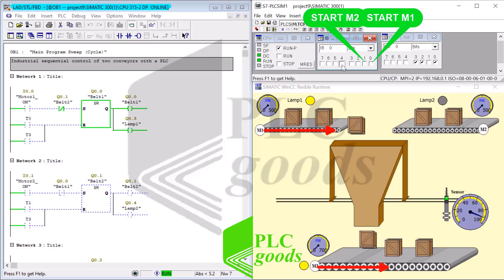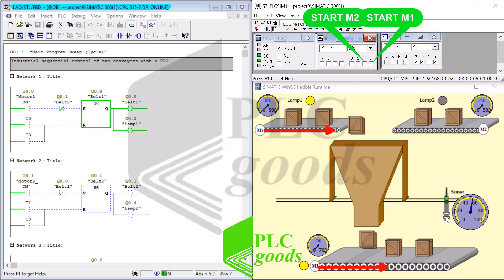According to the project specification, M1 and M2 cannot be on simultaneously. Right now M1 is on — I cannot turn on M2 by tapping on the I4 sensor input. In general, the system can shut down in two ways: either by pressing any related stop push button, or due to the absence of sensor detection within a 10-second time frame.